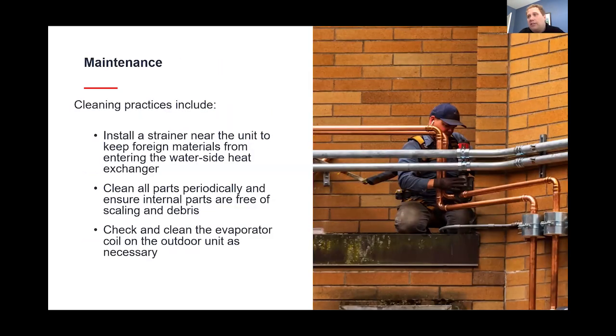And just one additional thing in terms of maintenance. These aren't going to be maintenance heavy products like other systems can be. It's really going to have a strainer installed near the unit to keep foreign materials out, so you have to clean that and make sure it's good. And then you're going to have proper tank maintenance like you would with any other product. You're going to have to clean the products and periodically ensure internal parts are free from scaling and debris, and then check and clean the evaporator coil as necessary.